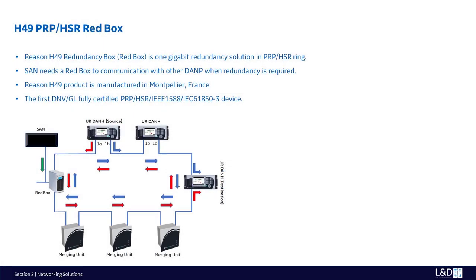The Reason H49 Redundancy Box, or Red Box, is GE's all-in-one gigabit redundancy solution. It has been especially designed for the digital substation for use on the substation bus and process bus. In a mix of PRP dual star and HSR high availability seamless redundancy rings, the gigabit HSR ring allows the transport of multiple sample values streamed on the same ring, simplifying the network topology. Why do we need a Red Box?